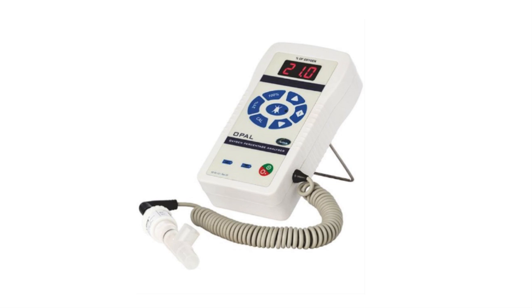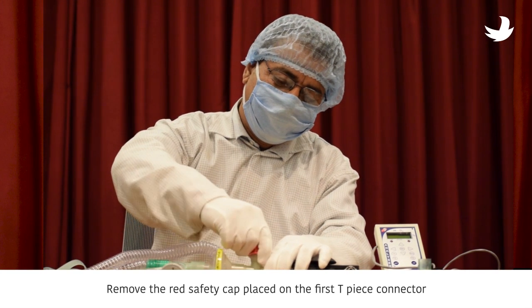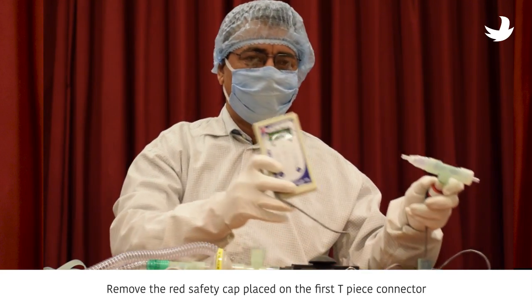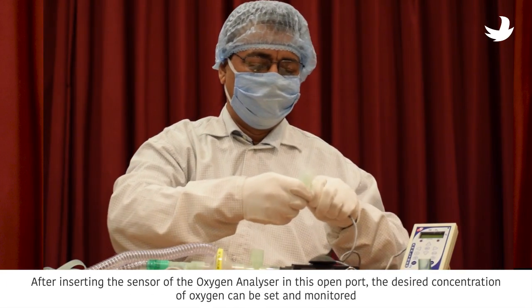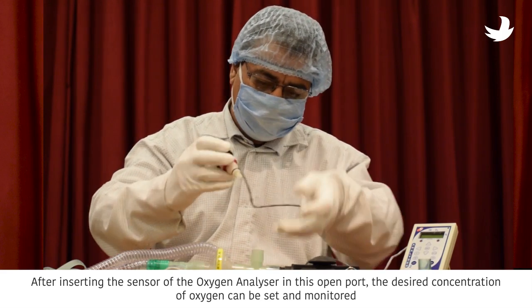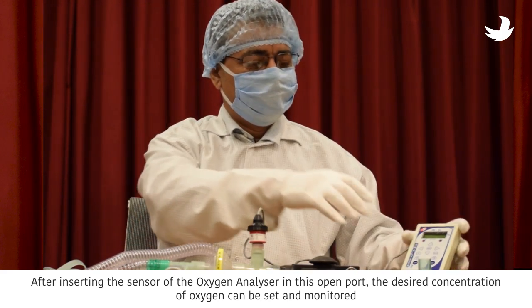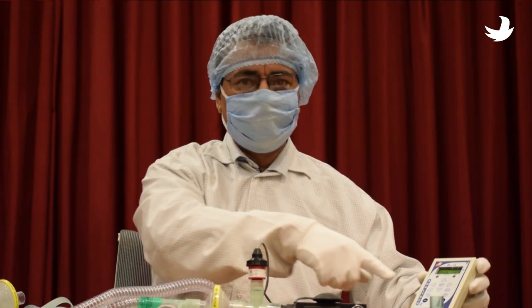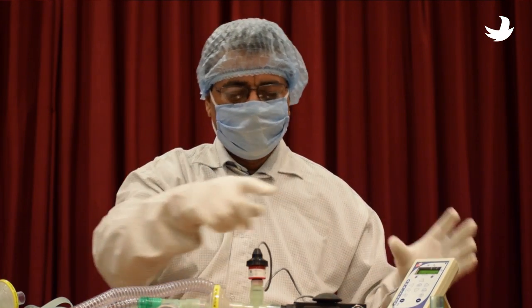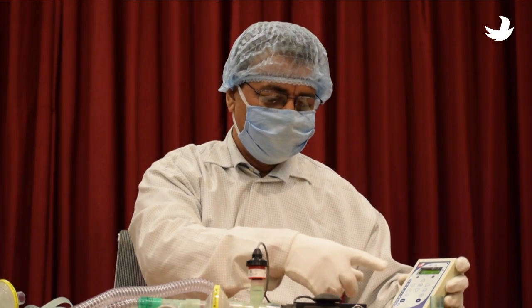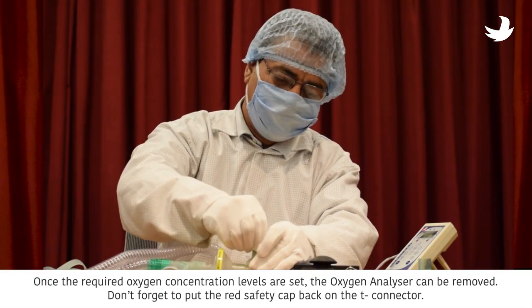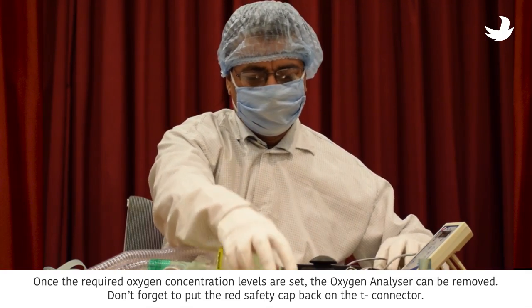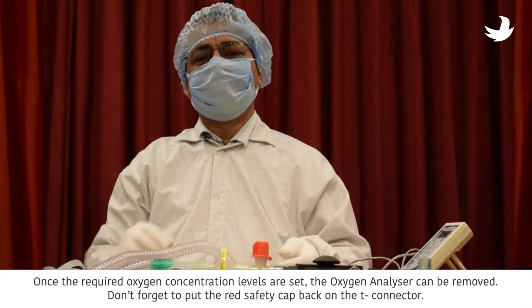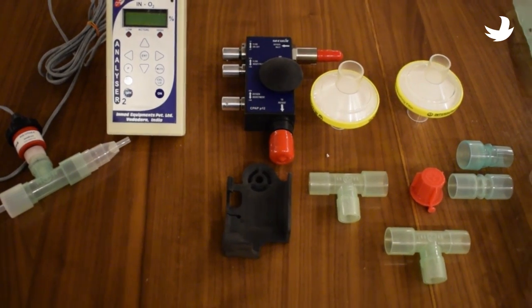When the CPAP P12 device is in use for a COVID-19 patient, the oxygen concentration needs to be set and checked. To do so, a clinical assistant needs to remove the red safety cap placed on the first T-piece connector in the patient circuit assembly. After inserting the sensor of the oxygen analyzer in this open port, the desired concentration of oxygen can be set and monitored. With the help of the control valves on the CPAP P12 device, one can set the required air-oxygen mix. Once the required oxygen concentration levels are set, the oxygen analyzer can be removed. Remember to put the red safety cap back on the T connector.